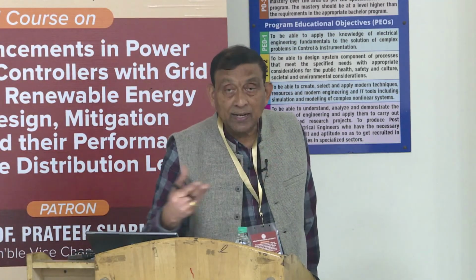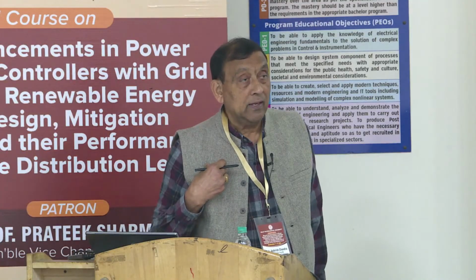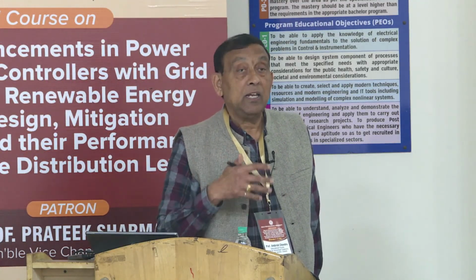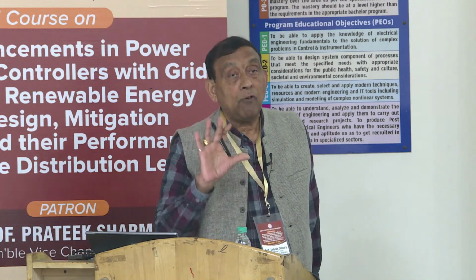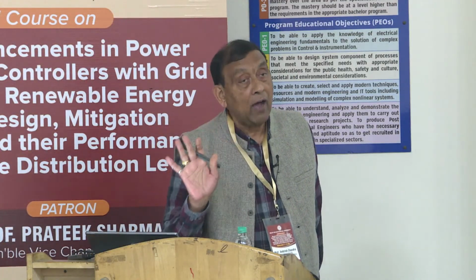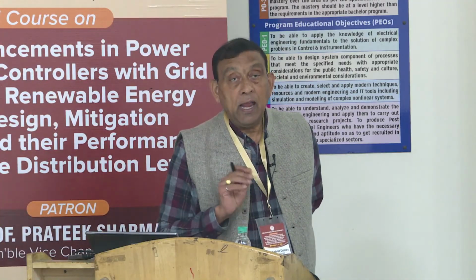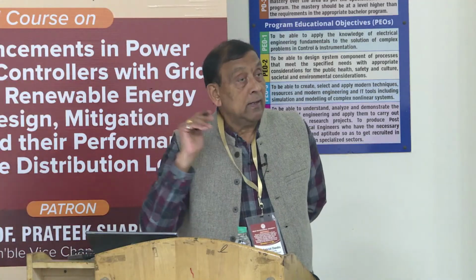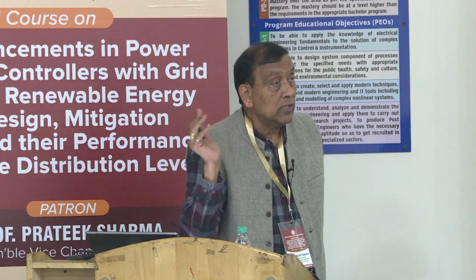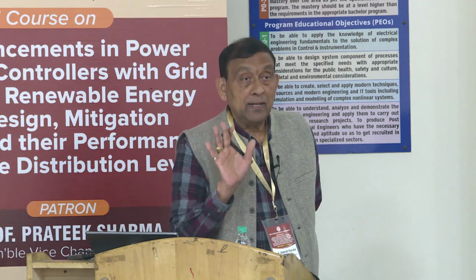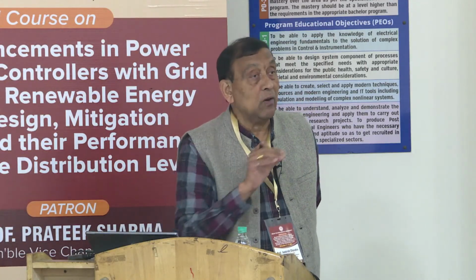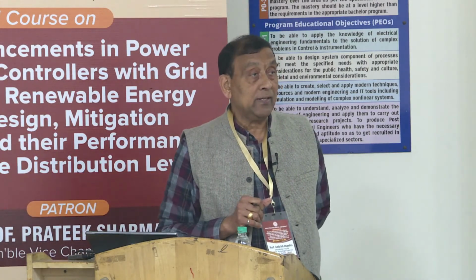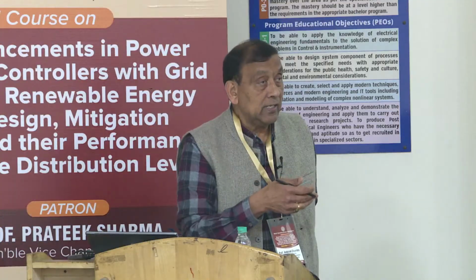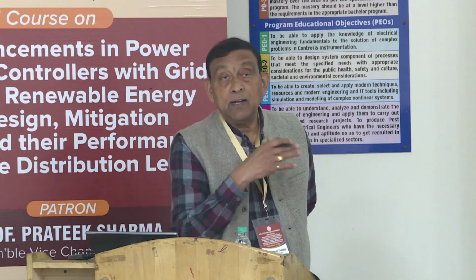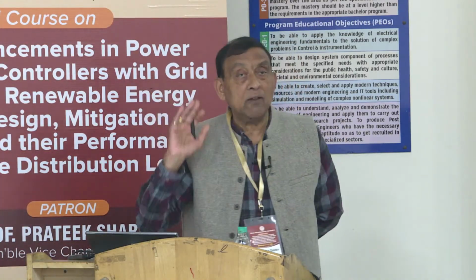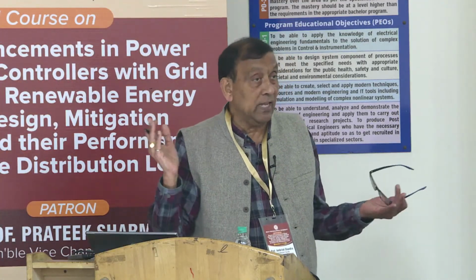Now the time comes to put in the second line of production, and that is the time an engineer has to see seriously whatever non-linear load you have, what kind of harmonics are generated by that load and how much, and they are going to the primary side and spreading around the internal distribution system of the plant. Presently this is not serious, but if you put the second line or third line of production, it becomes a serious matter. So if the engineer says, okay, the first line of production we already have is not giving much problem, so we can buy the same equipment for the second line.